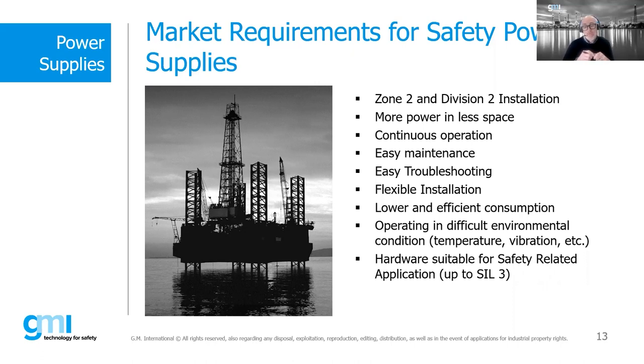Also, in the event of a failure, you need easy access to all device data to deal with the problem quickly and effectively. Unwanted or undesirable behavior, or the lack of a specific functionality, must be highlighted and easily diagnosed. The diagnostic module on board the GMI power supply system allows us to have all the required data under control and to be able to transfer them via Modbus or via digital contact to a dedicated system. This functionality allows us to have easy troubleshooting of our system and loop.